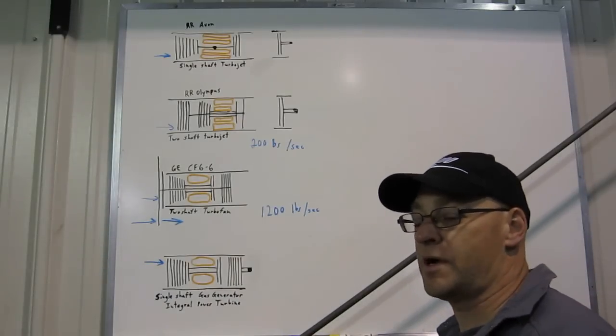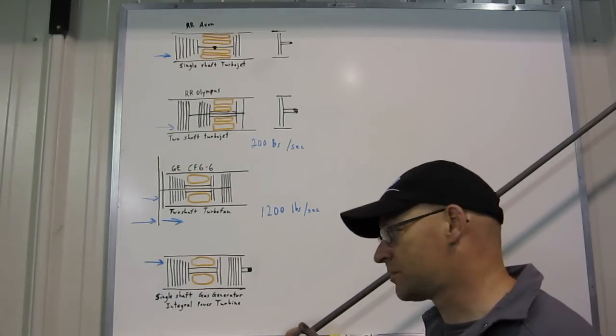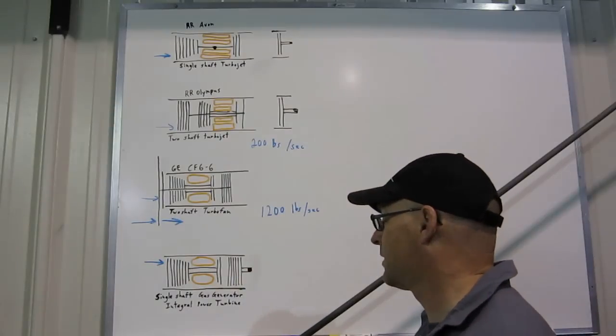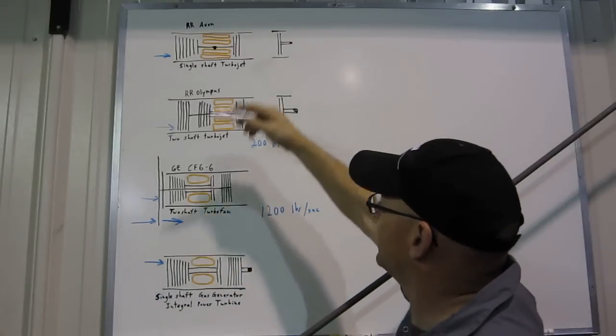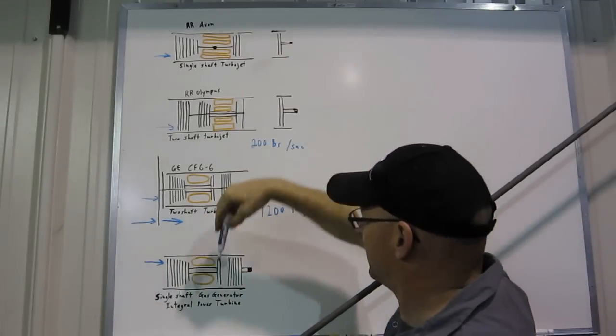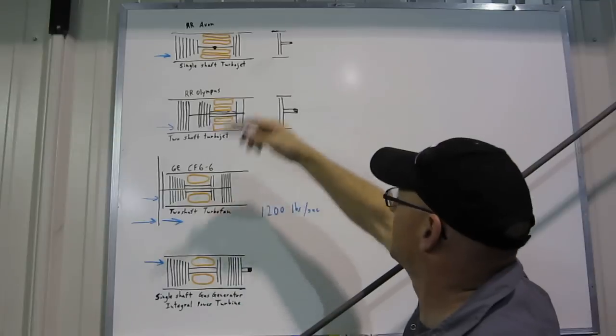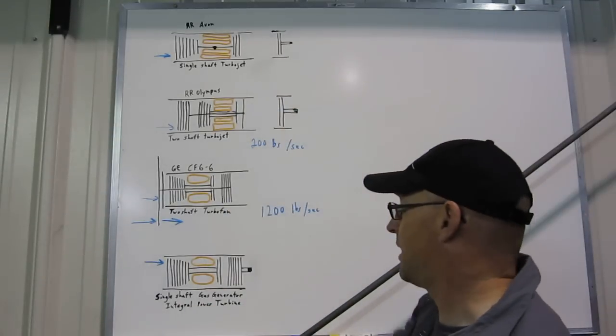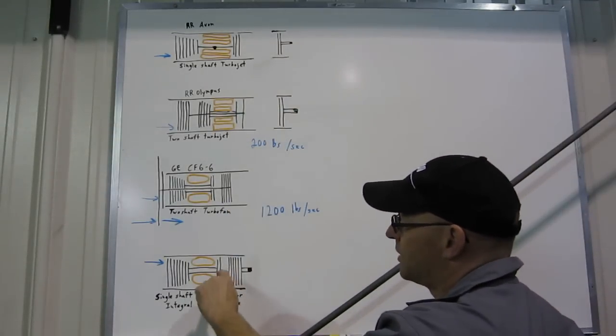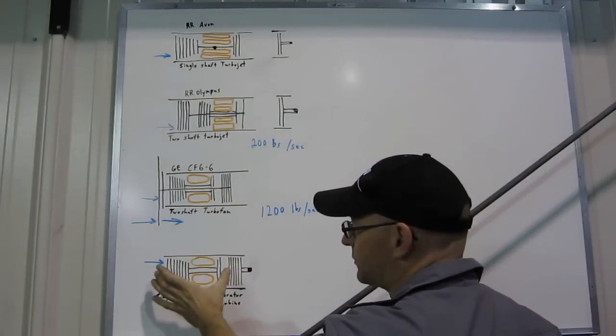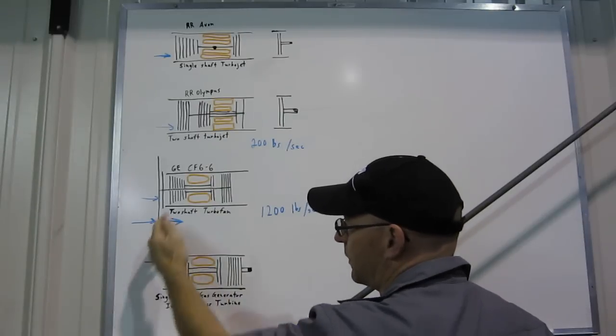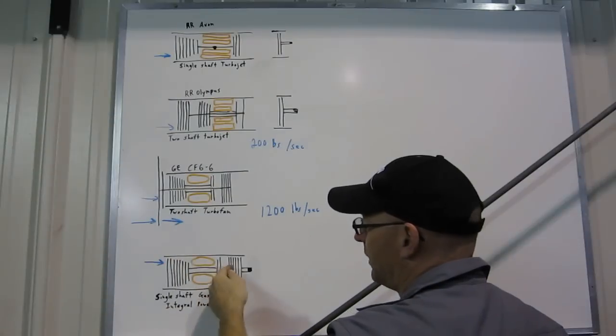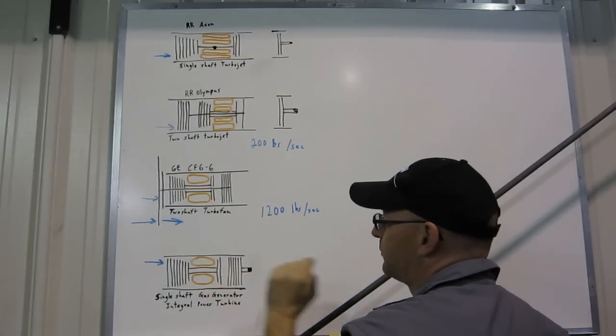Low-pressure turbine, it's also technically called the low-pressure turbine, but it's referred to as the power turbine. It's integral with the engine, which makes this engine different from the Avon, because the power turbine is part of the engine. Here, it's an extra piece of equipment that you attach, but it's very similar. So one of the systems, the low-pressure system, the compressor part has been removed, and the turbine's been modified so the output's at the rear.